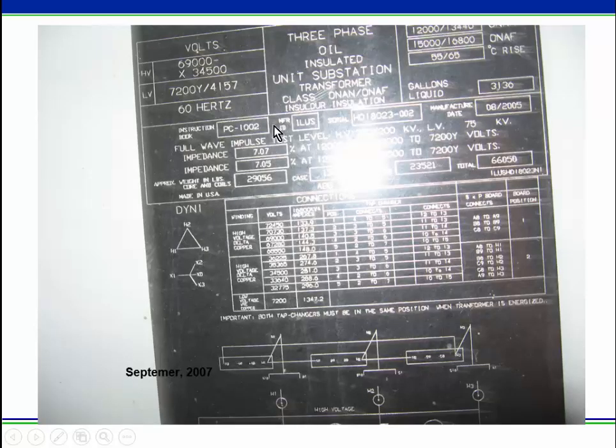Here's a substation transformer. This came out of Antelope Substation. I apologize, it's not the best drawing. Delta Y, notice again, H1, H2, H3 on the primary, the high side. And then here's the low side, X's. This HV means the high voltage, LV low voltage. And notice this X. This X means it's a dual voltage transformer. There's a switch in here that you can put the windings in parallel or in series, just like a motor. Remember how motors were done.